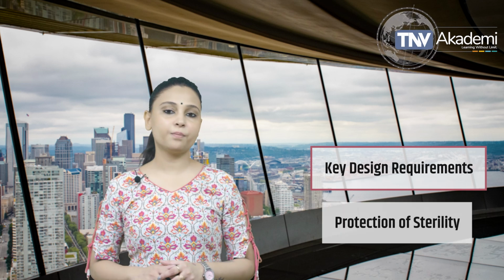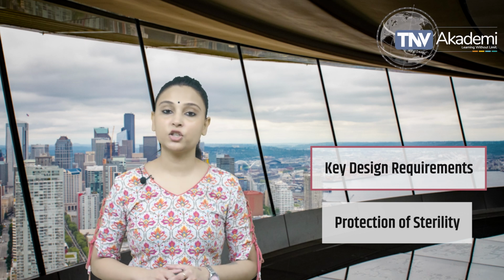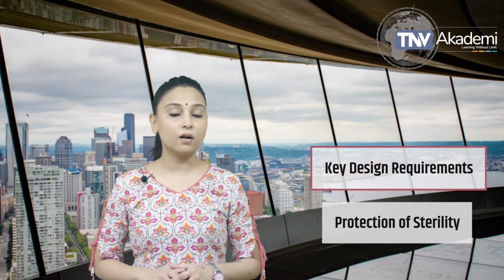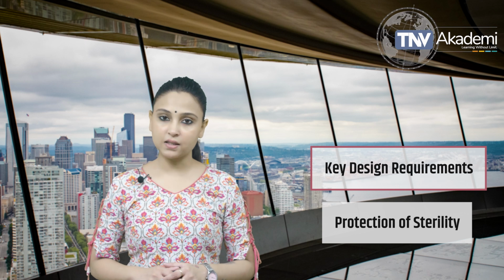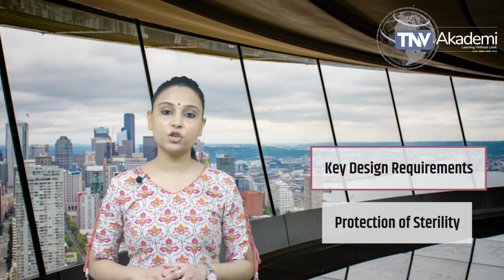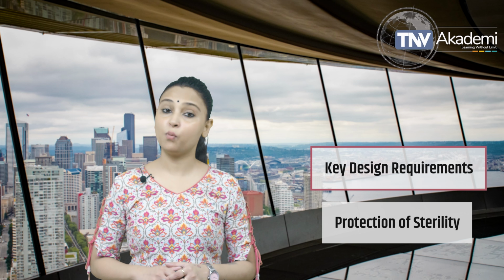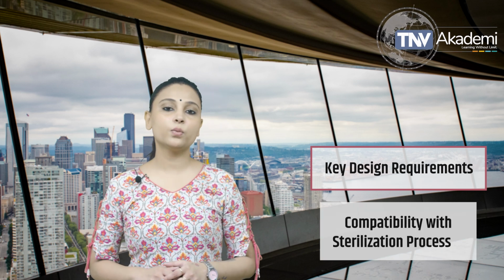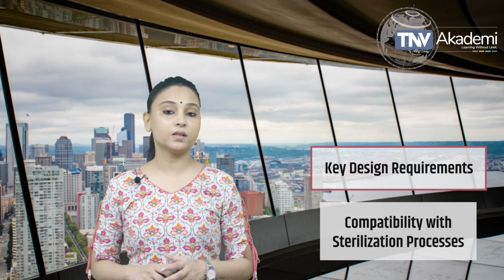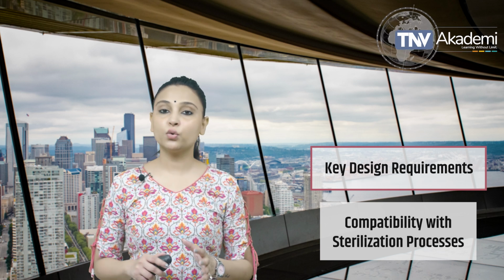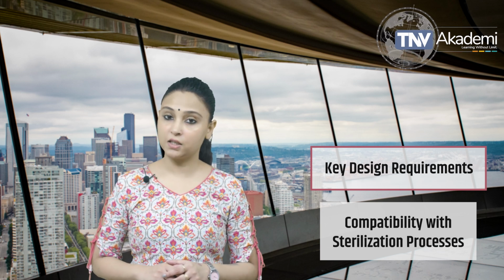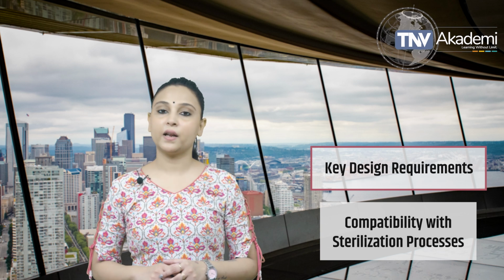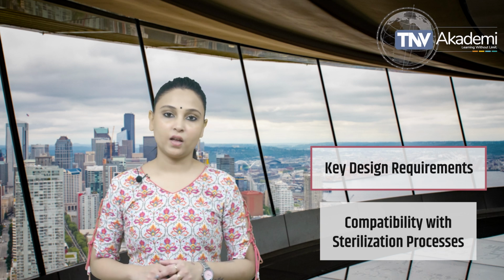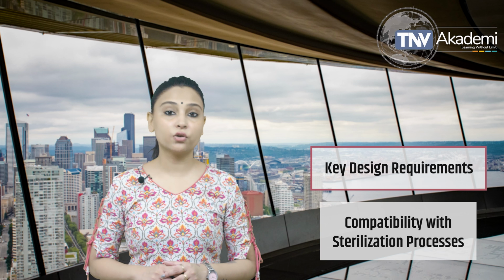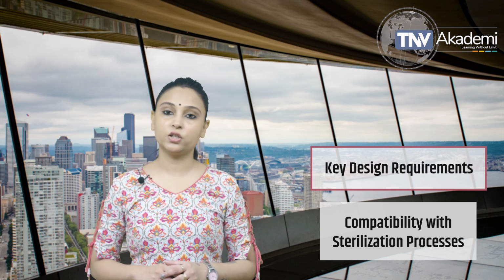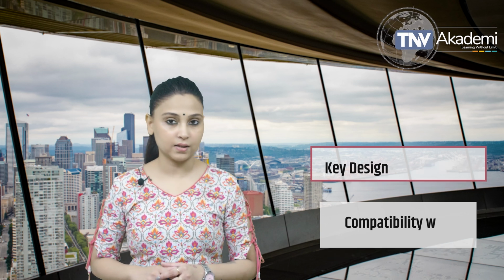The primary purpose of the packaging system is to protect the sterility of the medical device. This involves selecting materials and designs that prevent microbial contamination and maintain sterility until the point of use. Compatibility with sterilization processes. The design must be compatible with the chosen sterilization method, whether it be steam, ethylene oxide, gamma radiation, or another process. The materials and design should not degrade or compromise the sterility during and after the sterilization process.